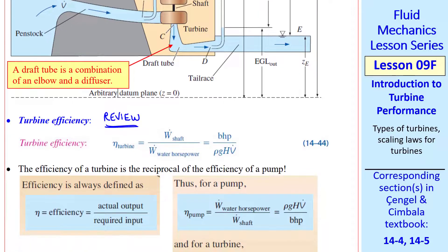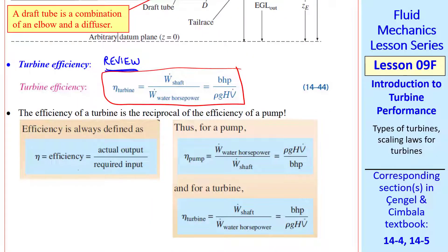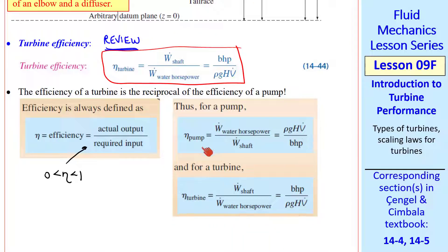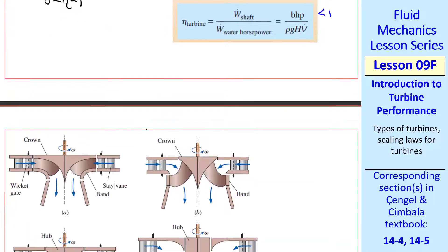I'll do a quick review of turbine efficiency. We define turbine efficiency as shaft power over water horsepower, or BHP over ρgHV̇. We always define efficiency as actual output over required input so that η is between 0 and 1. Compared to a pump, turbine efficiency is the reciprocal of pump efficiency — for a pump we put in brake horsepower to get water horsepower out, whereas for a turbine the shaft power is the desired output and we need more water horsepower to get it. Turbine efficiencies can actually be quite large; I've worked on turbines where the efficiency was greater than 95%.